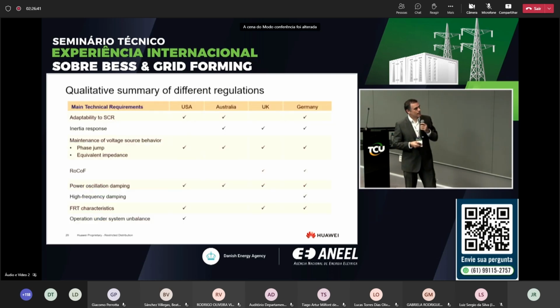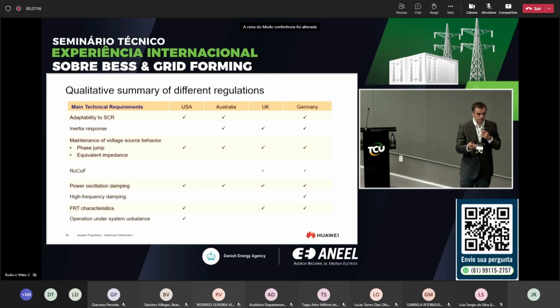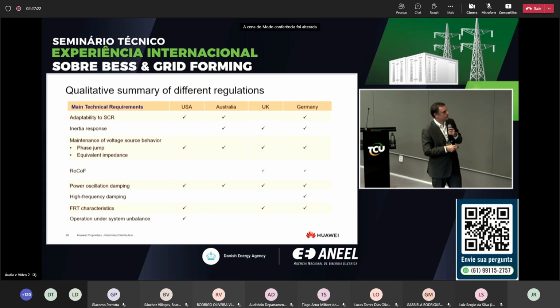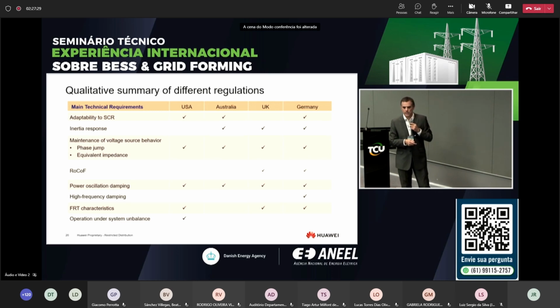I have gone fast through it, but some qualitative summary of what we have seen: mostly that we need to work with very low short-circuit ratio, we need to provide inertia, we have to prove voltage source behavior, react to the rate of change of frequency, provide power oscillation damping, and fault ride-through, and operation under system unbalance. In most countries right now, they are focused just on symmetrical component or balanced events, but in the US, they are talking about unbalance as well.